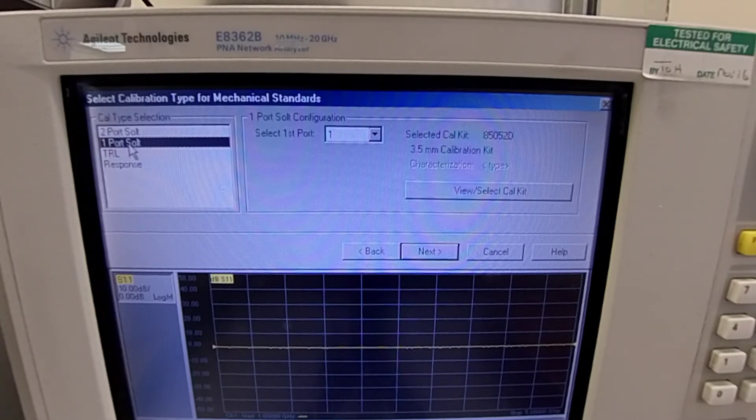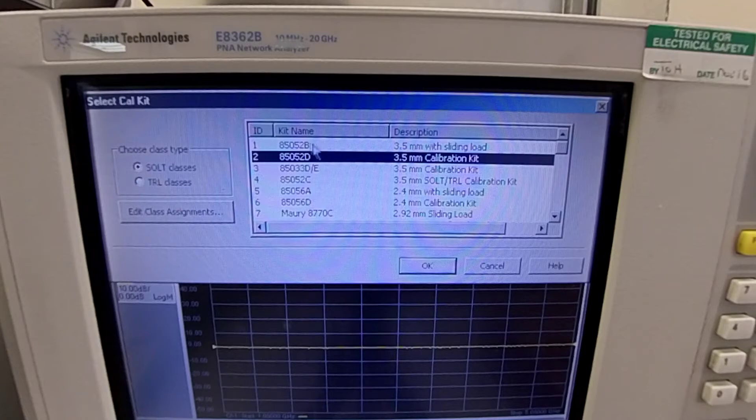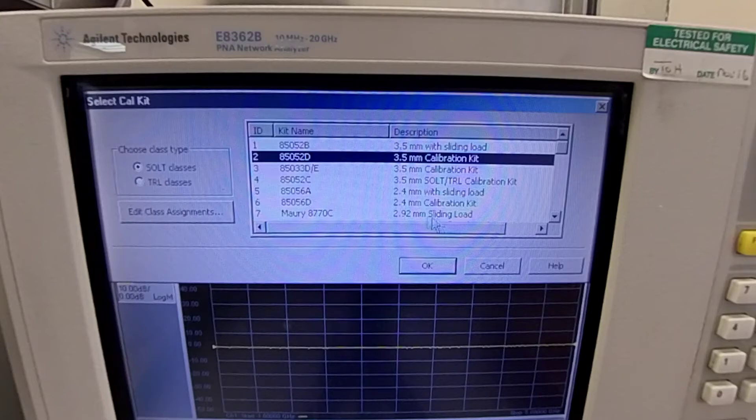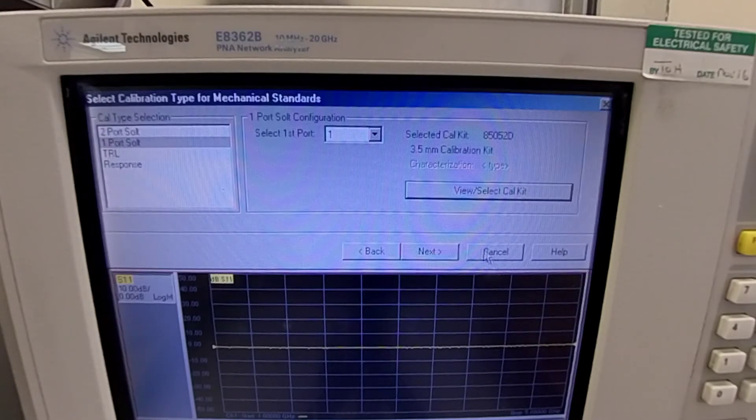We will select a one port SOLT calibration. SOLT stands for short, open, load, and through. The calibration kit by default is selected as 85052D which we are using right now. You can select other calibration kits from the menu if you have other than this calibration kit. We will start off with the calibration. Click next.